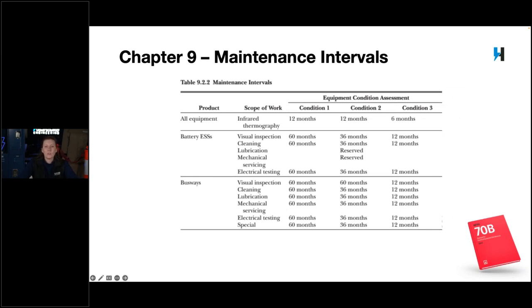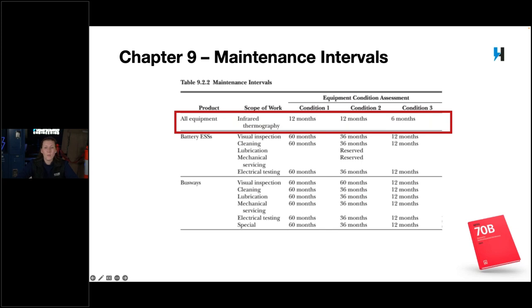So the maintenance intervals - all electrical equipment needs to have an infrared thermography scan performed. For condition 1 and 2, it's the same: every year. Condition 3 is every 6 months. So what do the different conditions mean - every year or every 6 months? How do you determine what your equipment needs?